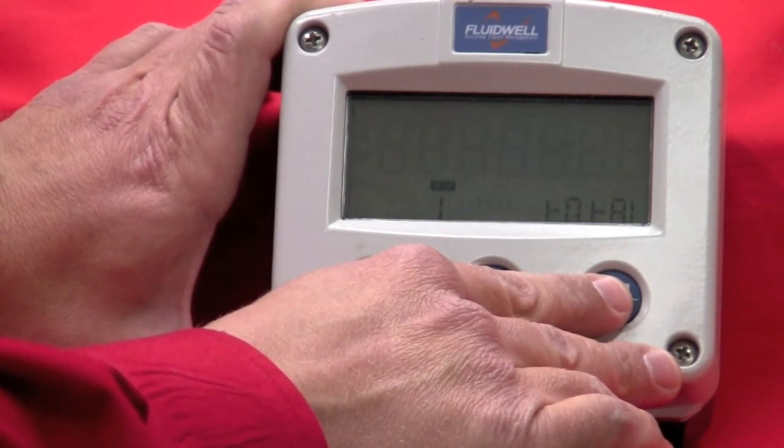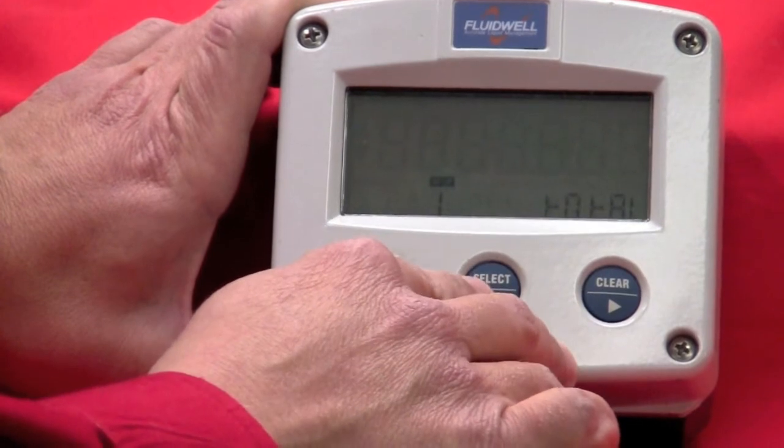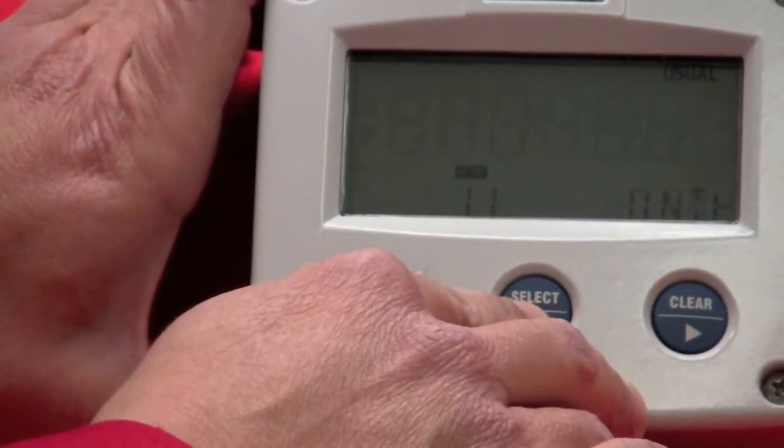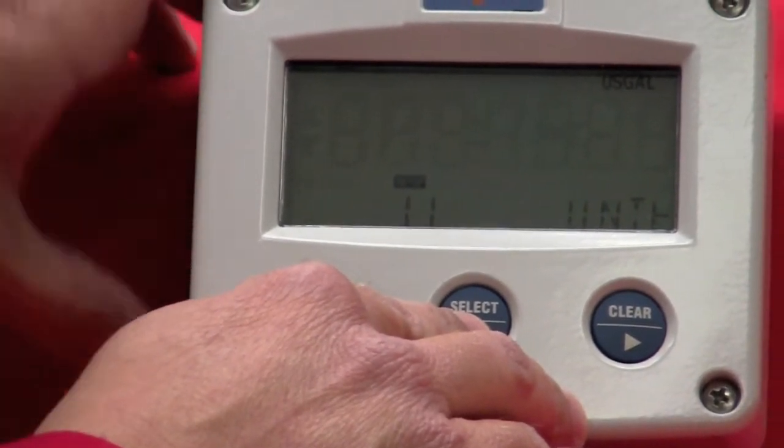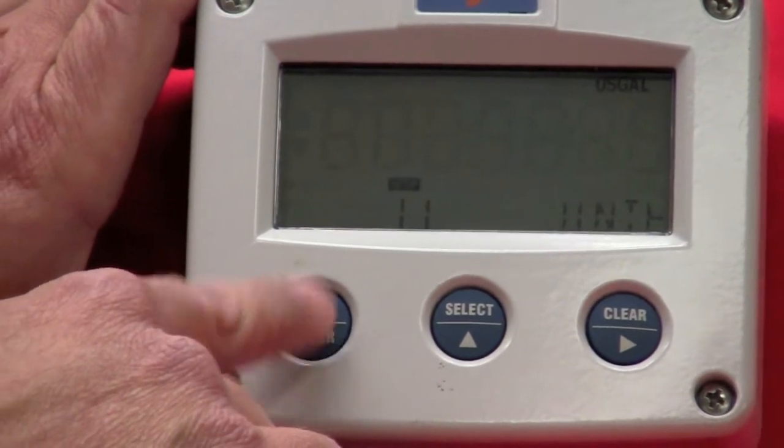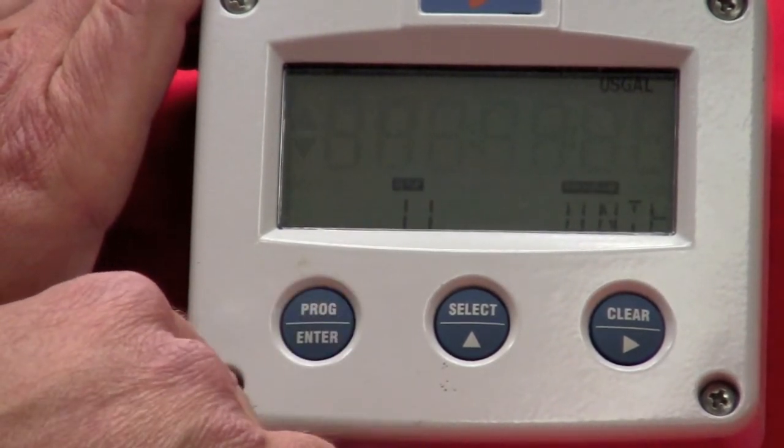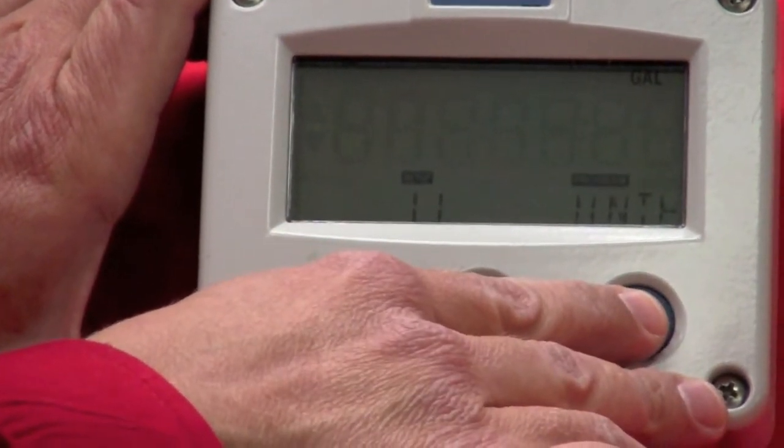To set the meter up and configure it, to drop into any of the main menus here, you're going to utilize your select key. So I'll hit it once. You'll see units. Now to program it or change the units, right now I'm in U.S. Gallons. To change that, just push and release the program key. You'll notice now I'm in Programs, Flashing, Units, and now I can scroll through the various units here.